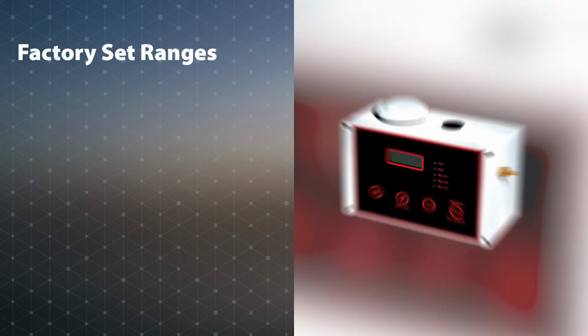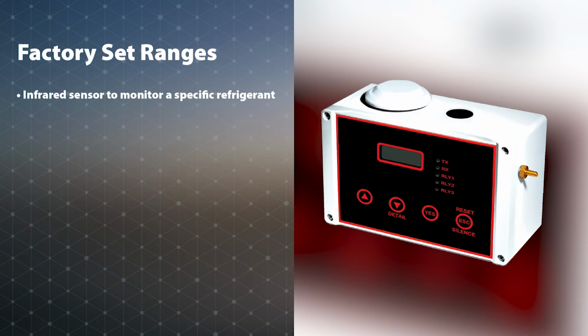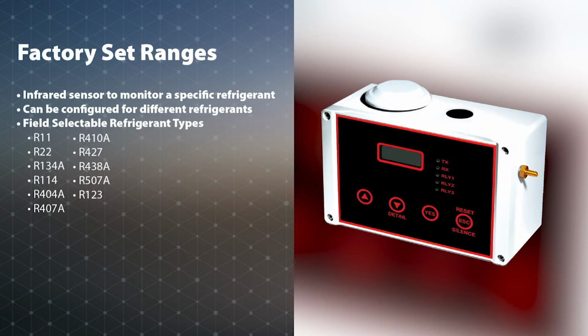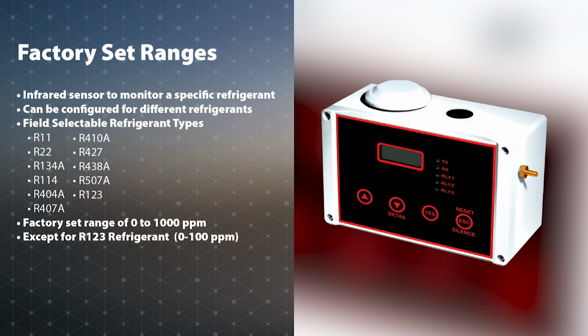The QIRF uses an infrared temperature-controlled sensor to monitor specific refrigerant, but can be field configured for many different Freon refrigerants, which gives greater flexibility during its installation. The QIRF has a factory set range of 0 to 1000 ppm for detected Freons, except R123, which has a range of 0 to 100 ppm.